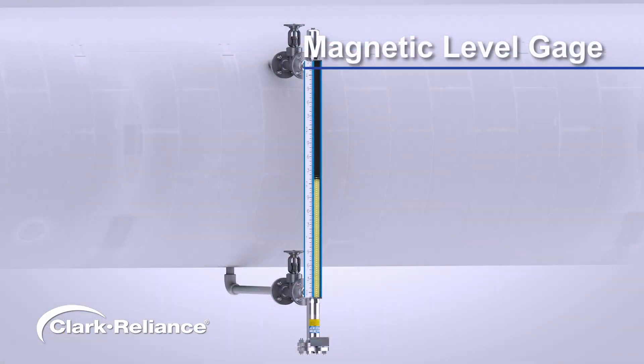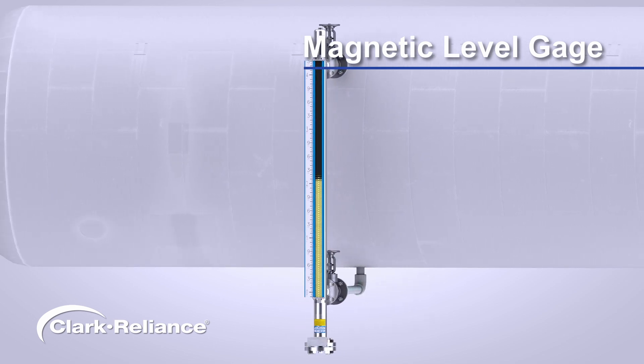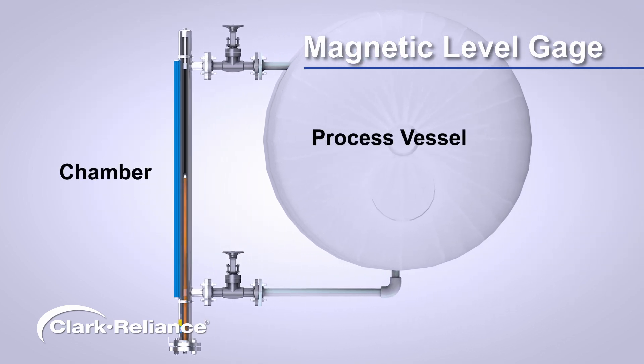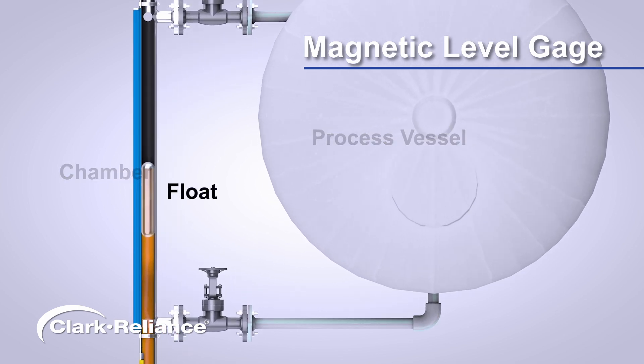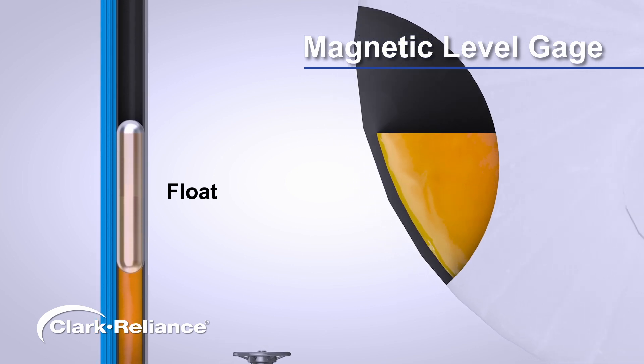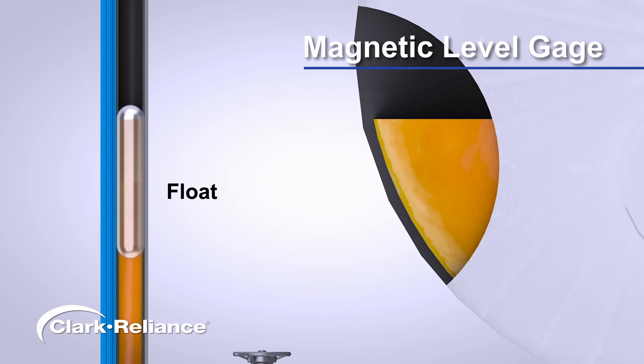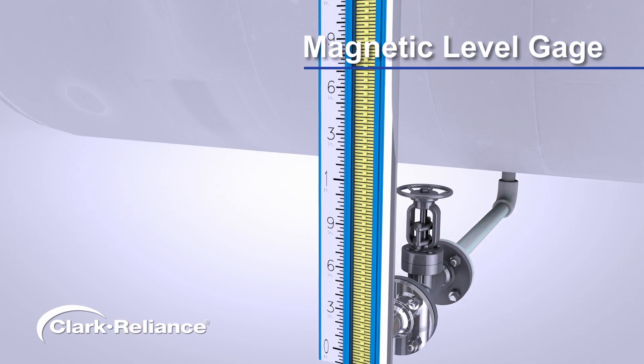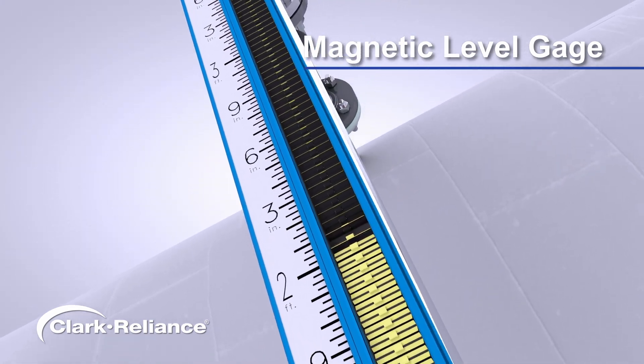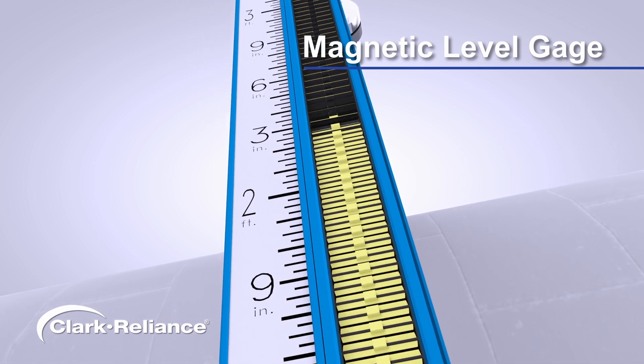A magnetic level gauge is a buoyancy-based level measurement device with high visibility. The magnetic level gauge chamber is connected to a process vessel. The chamber contains a sealed float with an internal magnet assembly which, due to buoyancy, rises and falls as the liquid level changes in the process vessel. The magnetic indicator is mounted externally on the chamber, completely isolated from process liquid. Indicator flags are rotated by the float magnet assembly as it moves with the liquid level.